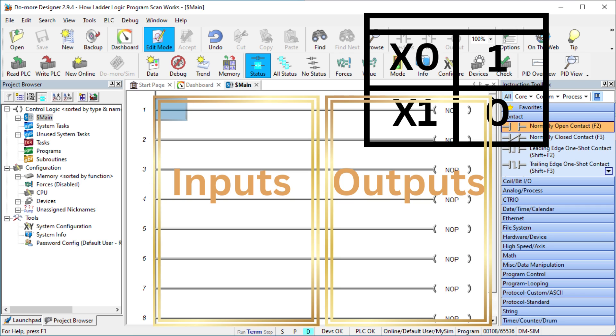If the input conditions are true, logic will flow from the left to the right. This will then activate or turn on the outputs for that rung. This will update the memory table. Ladder logic is solved from left to right, top to bottom.